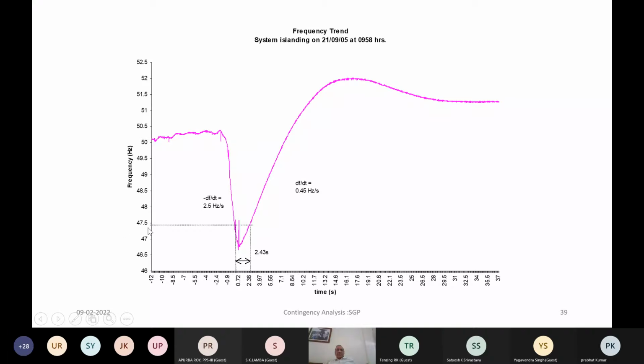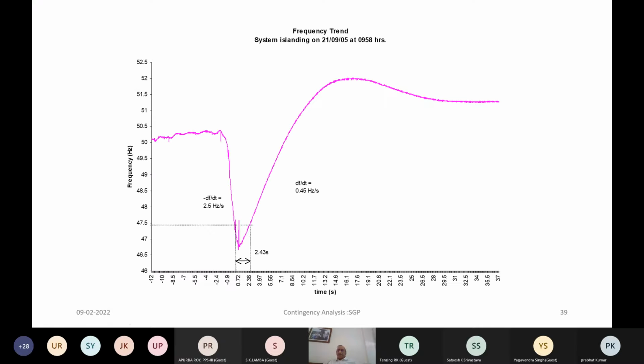So 47.5 being the lower limit of turbine trip, there should be sufficient time delay so that this recovery is possible. Otherwise, your generating station will trip at this instant only, and the island will collapse. So this is basically related to special protection schemes, which include the islanding scheme.